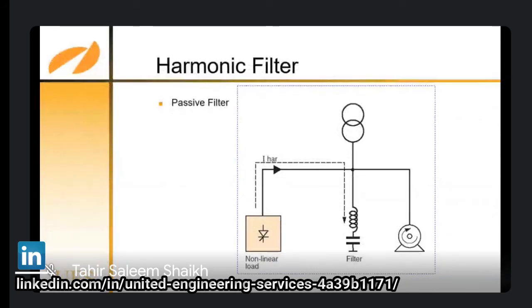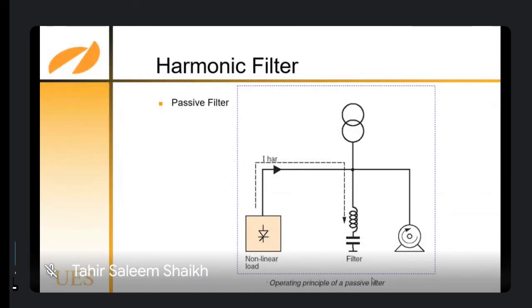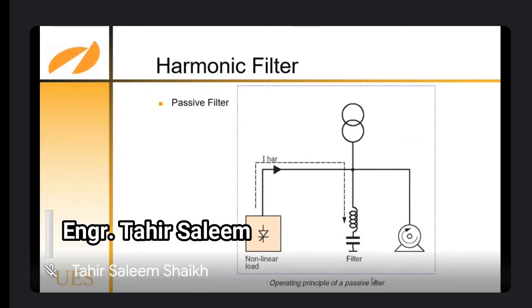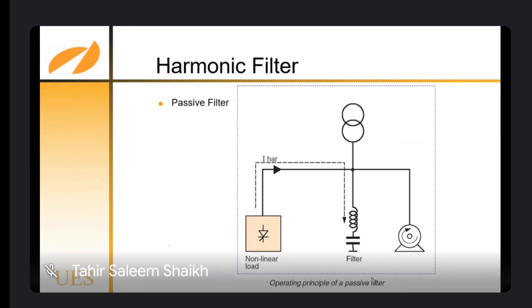You can see over here, this is the less expensive passive filter. The non-linear loads are grounded. And one thing is very important: if you are using a filter in a system, your earthing system must be perfect, like this. If your earthing system is not perfect, the harmonics recirculate in the system. So this is the easiest way, using a reactance and capacitor filter. This is called a passive filter.